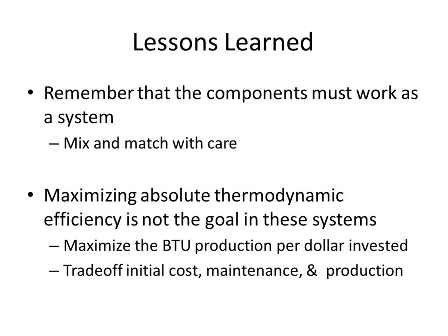Another thing to think about is that components have got to work as a system. In some cases, for them to work at all, not even to work well, you've got to make sure the components you're using, primarily the collectors, the heat exchanger, the pump, and the tubing that goes back and forth, are designed to work together. This is primarily because of heat transfer, both in the collectors, how quickly you're putting heat into your heat transfer fluid, and in your heat exchanger, how quickly you're pulling heat out of it. I'm not saying you have to use components all of the same brand, but when you're looking at a system, if you're not buying a pre-engineered one, you've got to take the time to look at how these components were designed to work most efficiently.